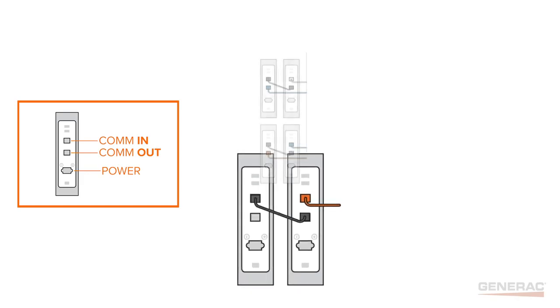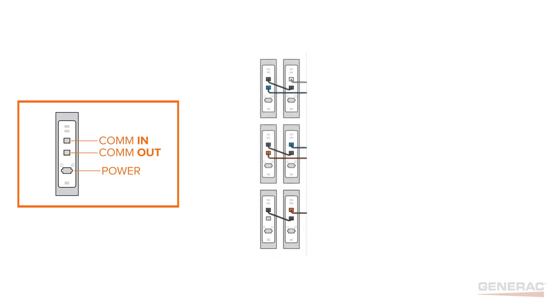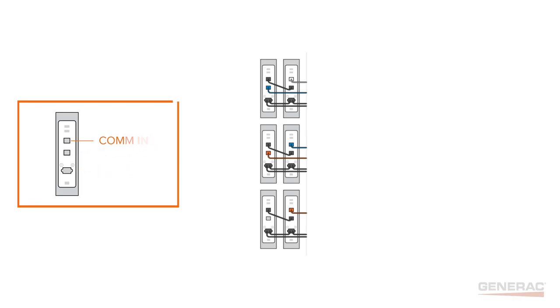With the communication cables connected, we can now install the power cables. If you have not already done so, remove the rubber stoppers from each installed module's power port. Now, connect each module to the power cable harness using the nearest plugs on the harness. A noticeable click indicates a good, solid connection.